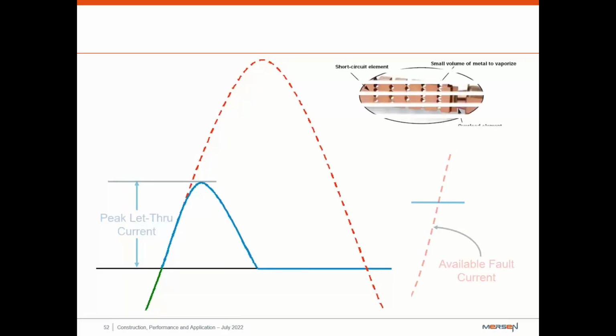And this is going to be during normal operation. This is the short circuit current element. You can see that all the holes are open. There's no issues. The overload element is going to be on the side. You can notice that there's going to be a small volume of metal here. What happens is that's going to vaporize once it reaches too high of a current. So let's take a look at a fault.